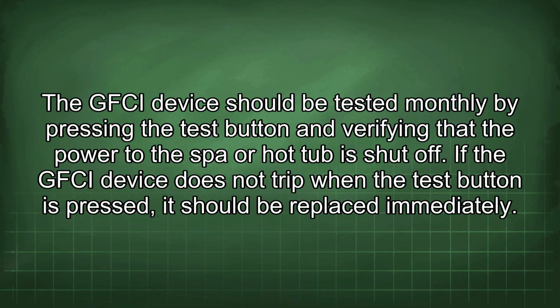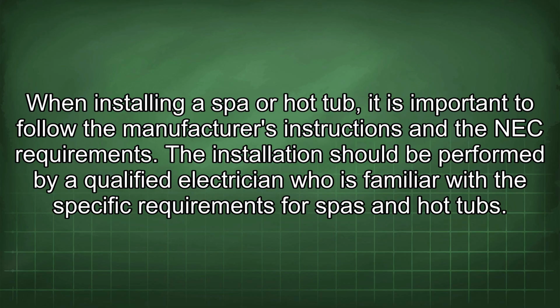The GFCI device should be tested monthly by pressing the test button and verifying that the power to the spa or hot tub is shut off. If the GFCI device does not trip when the test button is pressed, it should be replaced immediately. When installing a spa or hot tub, it is important to follow the manufacturer's instructions and the NEC requirements.